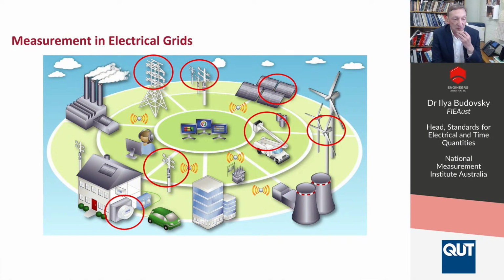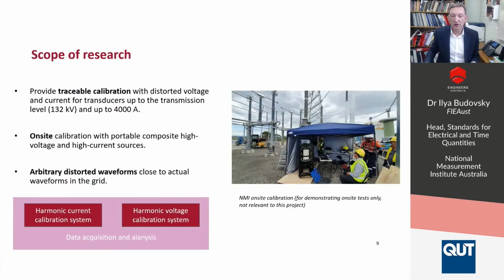So we found that at the National Measurement Institute, we had to apply our skills, our facilities and our experience to develop measurement systems that would make it easier to credibly measure harmonics in high voltage power lines and traceably characterize them. So, what do we have to do? We are working to provide traceable calibration for voltages up to 132 kilovolts and currents up to 4,000 amps.